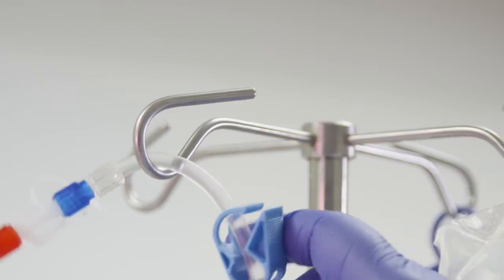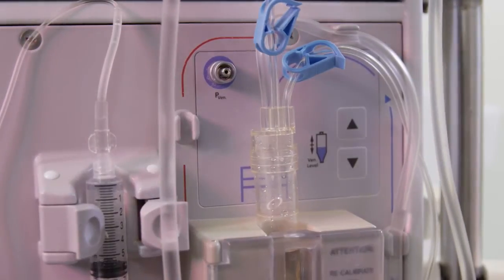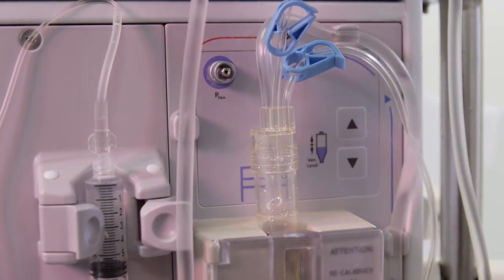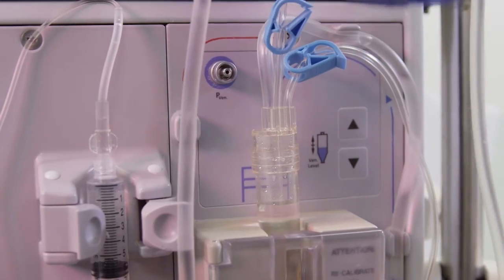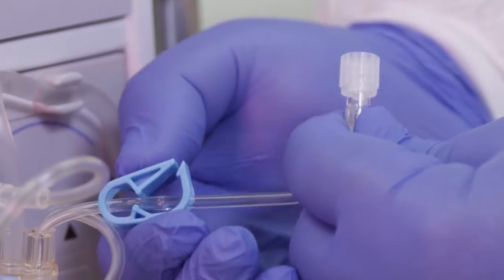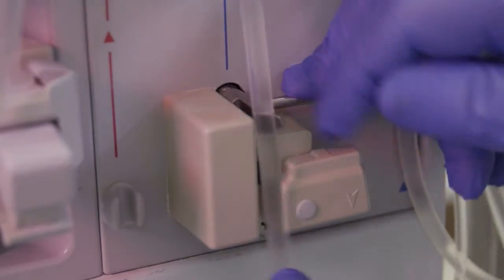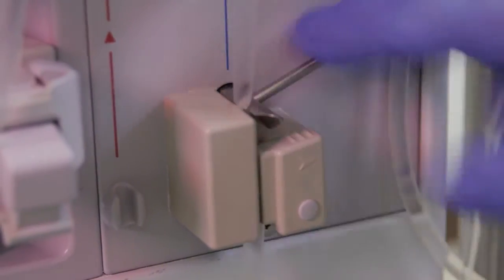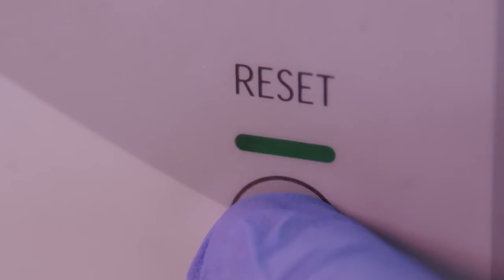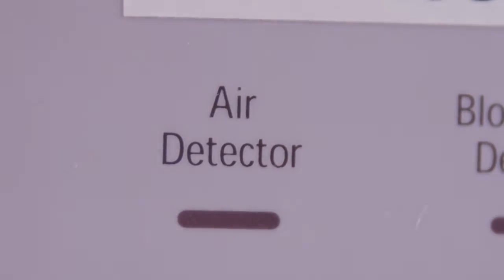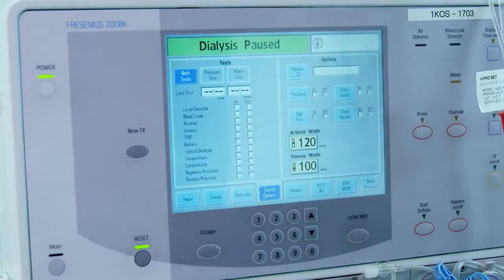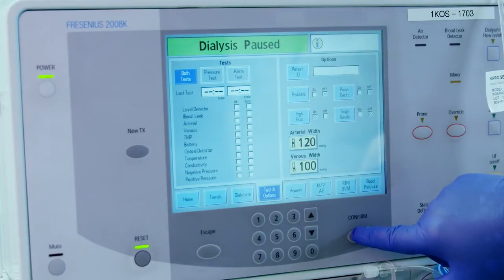Open the short infusion line clamp on the venous drip chamber and loosen the cap to allow the venous drip chamber to fill 3/4 full. Then tighten the cap and reclamp the line. Thread the venous tubing to the air detector. Press the reset button to clear the air detector alarm. Close the clamp on the saline administration set. Perform pressure holding and alarm tests on the machine.